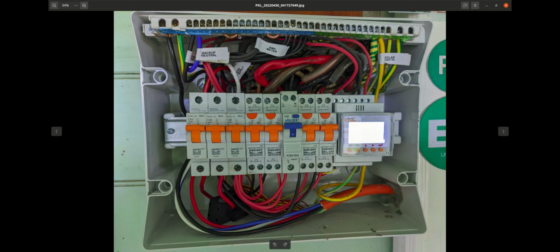I should point out that if you do separate the neutral bars for your backup circuits on the Alpha ESS, you get a different problem. If I pull that link out there, because all the Alpha ESS backup circuits are here, then you will find that your earth is like 120 volts to active and 120 volts to neutral. Because obviously the inverter is tapped halfway and grounded halfway. So that's a bit of an issue. So don't do that on the Alpha ESS. Don't separate your neutral. Now I can say goodbye. Bye.